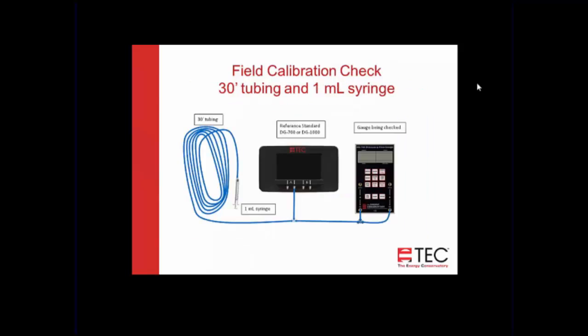And this is showing 30 feet of tubing and a 1 milliliter syringe. So now we're using a much smaller syringe, and we're not using that Magnehelic gauge as a buffer. The reason we switched to that is you don't have to have a mag gauge around, and this is also a closed system, so you don't have to worry about the pressures dropping.